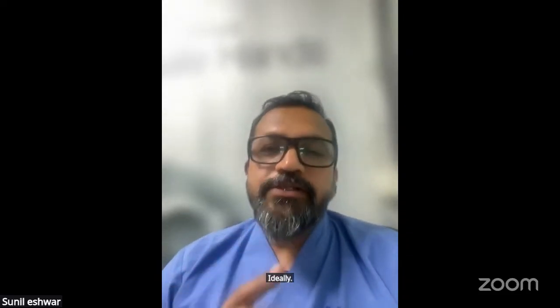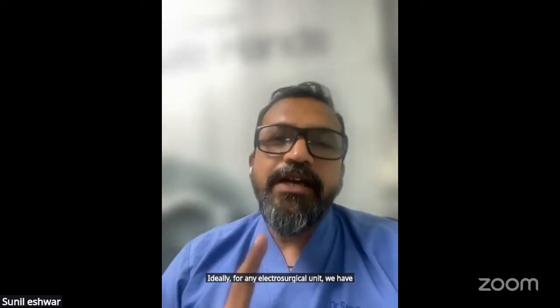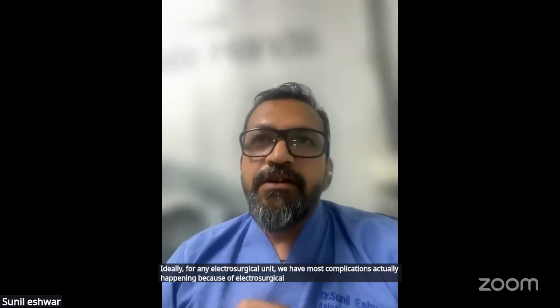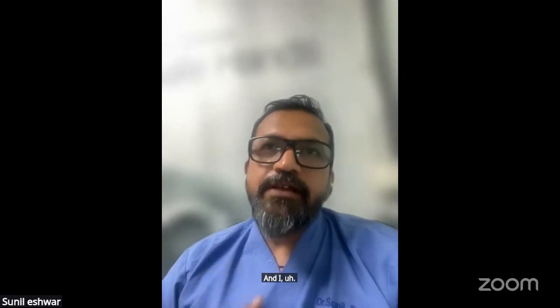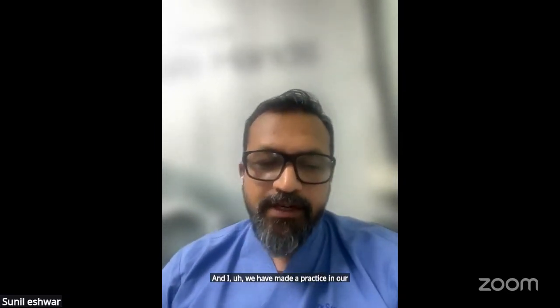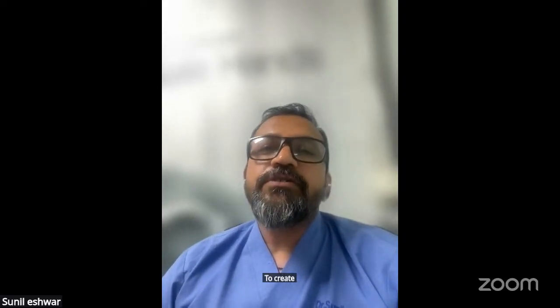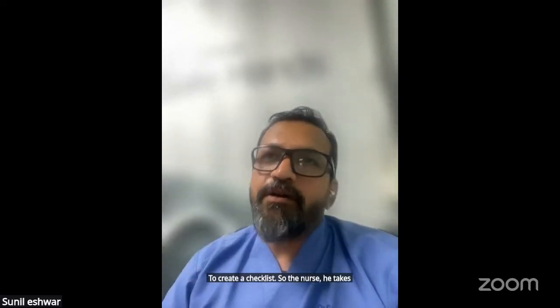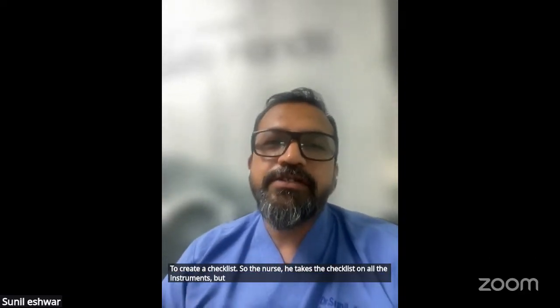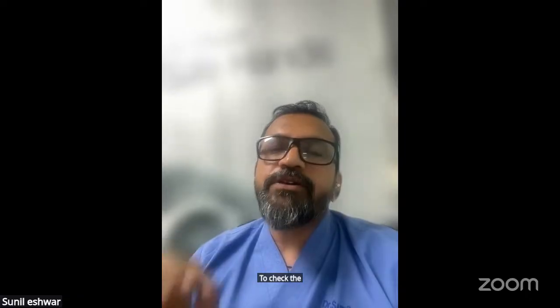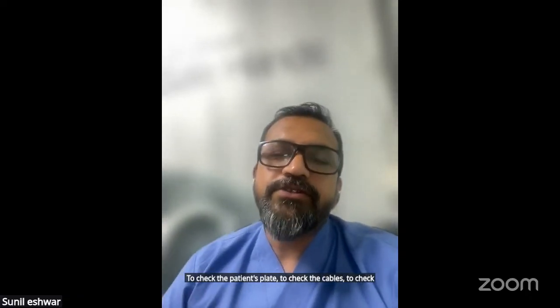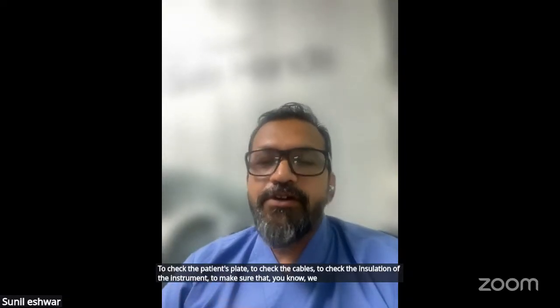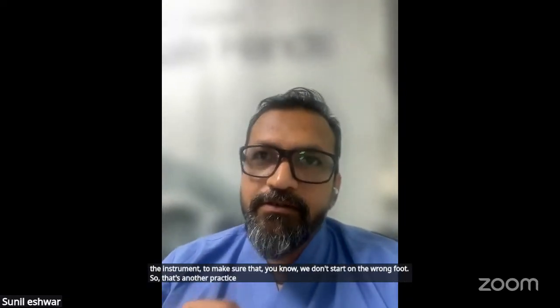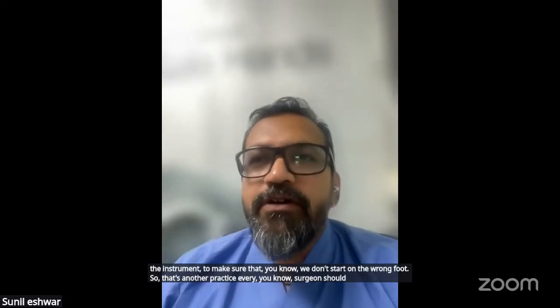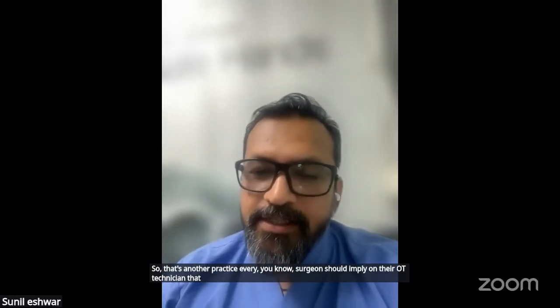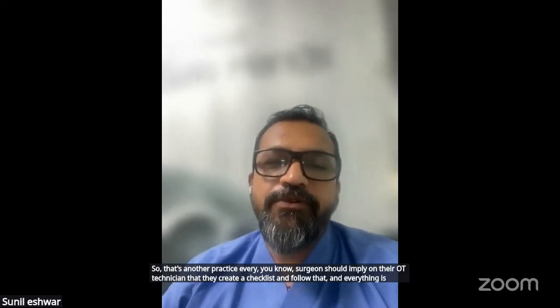Ideally, for any electrosurgical unit, we have most complications actually happening because of electrosurgical malfunction. And we have made a practice in our institute to create a checklist. So the nurse takes the checklist on all the instruments, but particularly on the electrosurgical units, to check the patient's plate, to check the cables, to check the insulation of the instrument, to make sure that we don't start on the wrong foot. So that's another practice every surgeon should imply on their OT technicians, that they create a checklist and follow that, and everything is tick marked before we start the procedure.